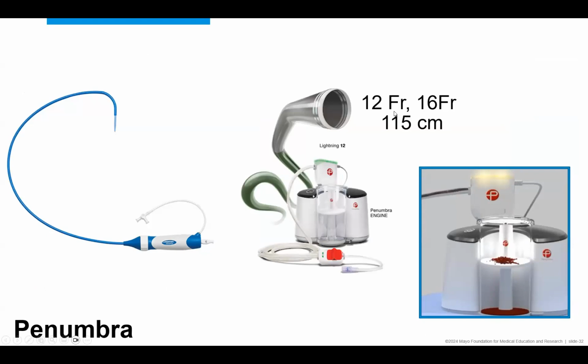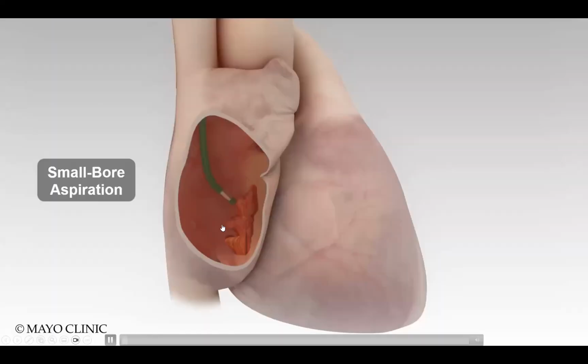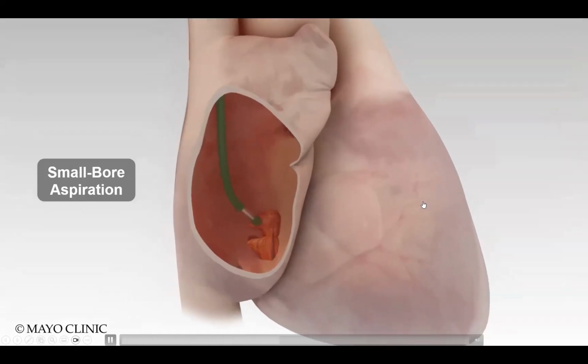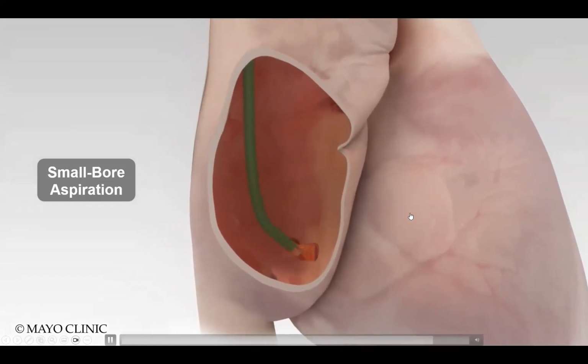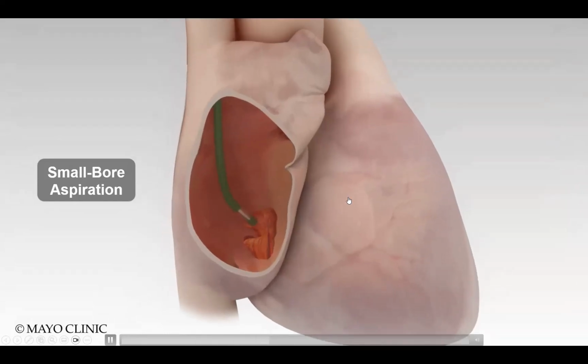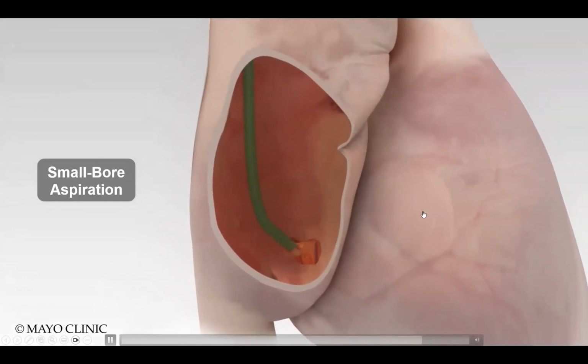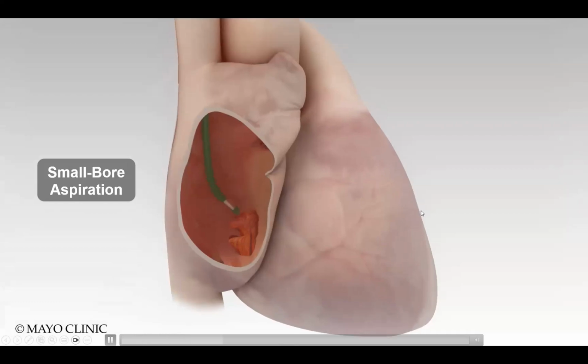Here's the smallest catheter that we have that we can use in these cases, and it's called the Penumbra. And basically, it's a tube connected to an engine that just pulls blood intermittently. Again, not continuous suction. Small. It's modest aspiration forces, and we can't return the blood here, so there's blood loss associated with this procedure. And this is how we use it. Small bore, so we have to contact these vegetations. The vegetation has to be small enough, but if it's large, then this is not effective to remove it.